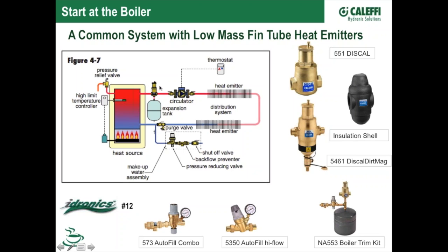That's the best, lowest solubility, and that's why we show with the circulator pumping away from this and the air removal device here, we've got that high temperature, we've got that low pressure area that'll help us get that out there. That's also an ideal place to add a fill valve. A lot of times the guys will just tee it right into the system here.